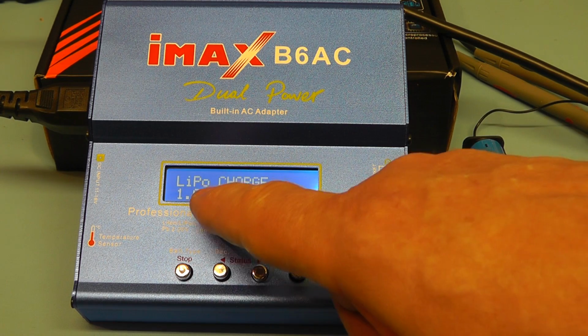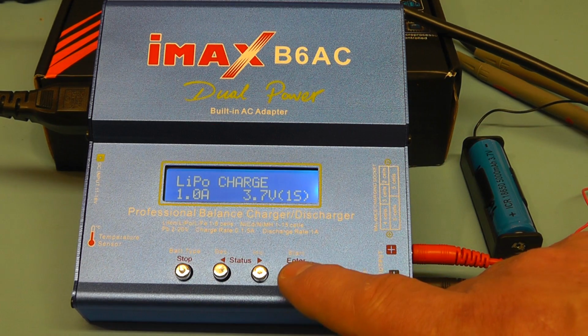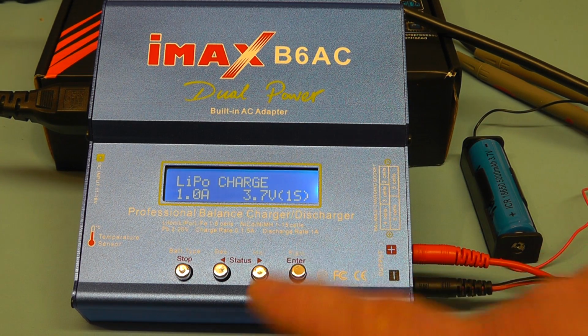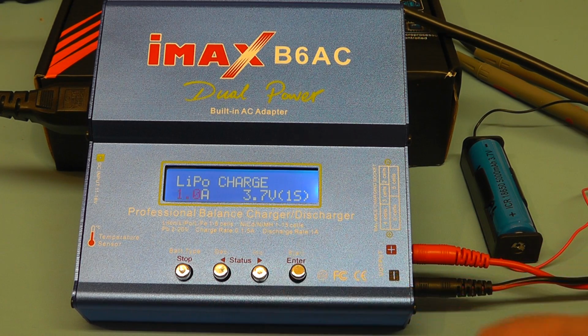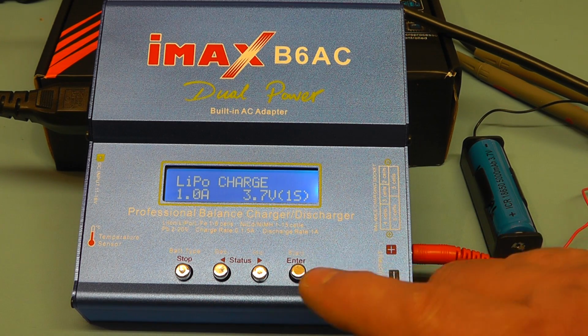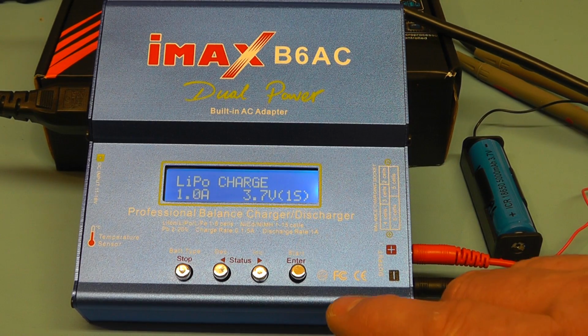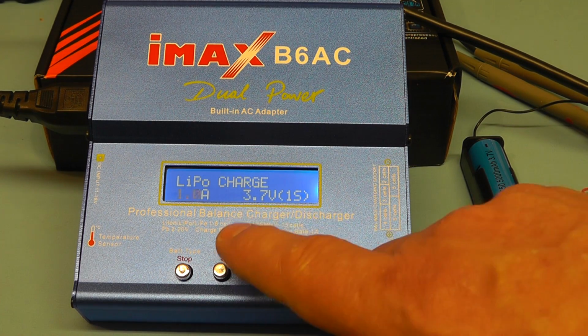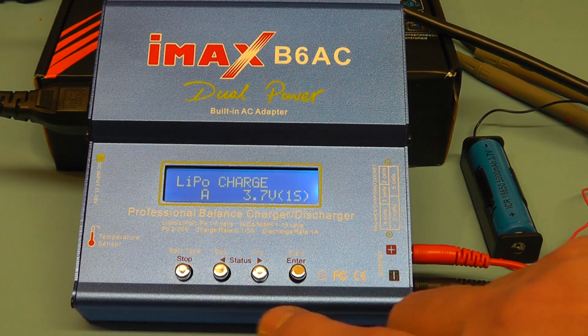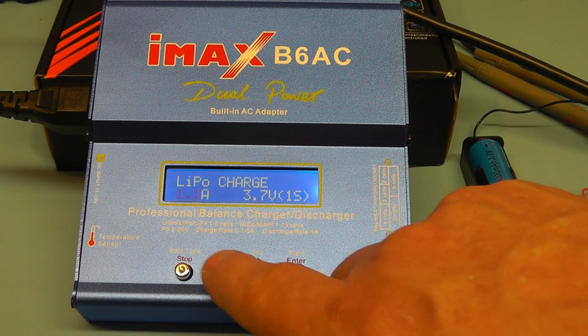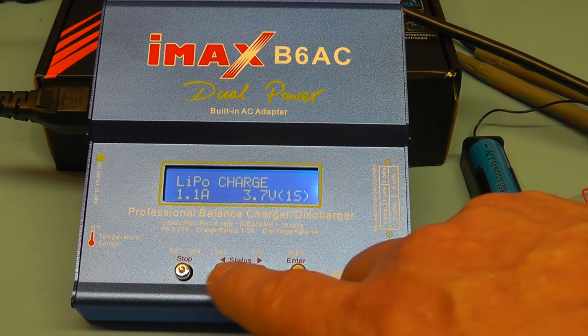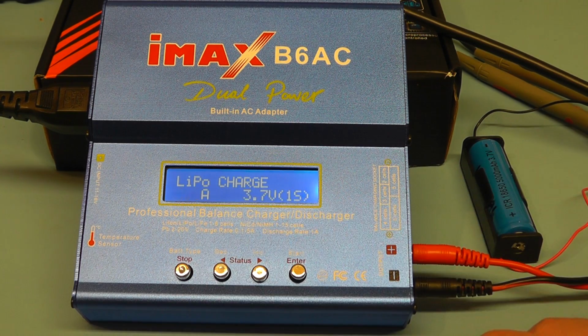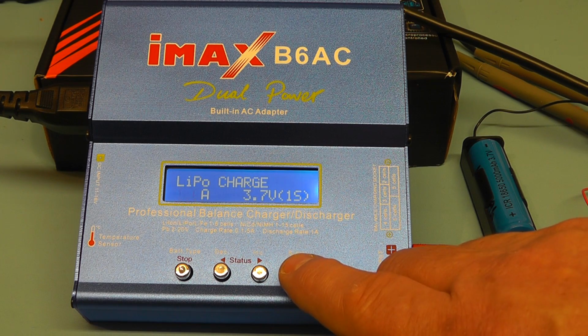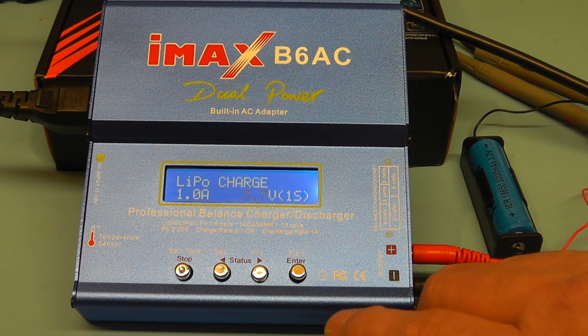To accept this we press start again. So we've accepted that option by pressing start again. Now the current indicator is flashing. You can increment or decrement that current using the increment and decrement buttons here, but we'll leave it set at 1 amp. Happy with that, you press the start button.